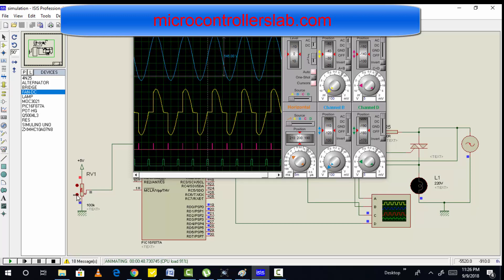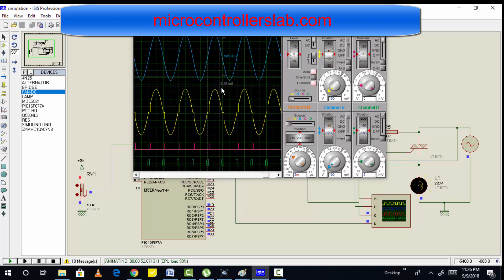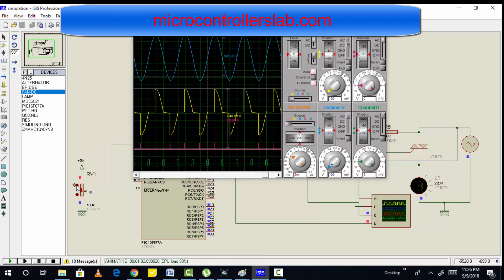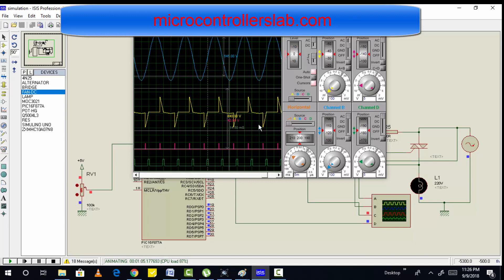Now let's decrease the firing angle more. This is the full waveform — you can see this firing angle is almost equivalent to this zero crossing, and we are getting full voltage across this induction motor. We are using a lamp as a demonstration of the induction motor. Similarly we can decrease the voltage as well — as you can see the firing angle is also delaying more and voltage is decreasing. We can increase and decrease the voltage across this induction motor, and for single phase induction motor we can easily control the speed by varying the voltage across it. This is true only for single phase induction motor.